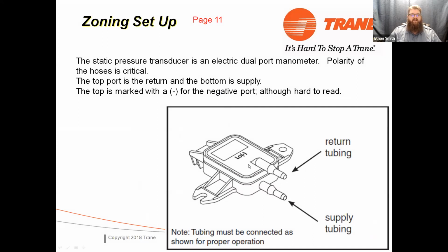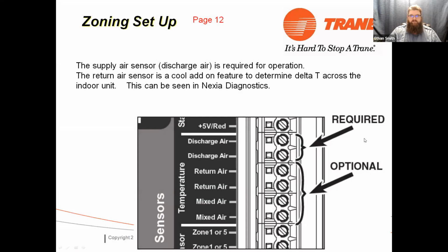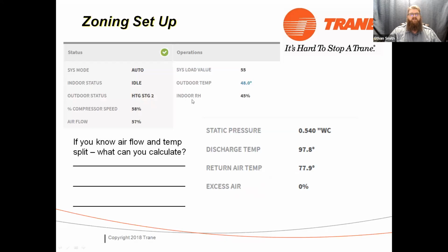It is polarity sensitive. You'll notice on the front of it, it says low or negative. That's going to go to our return pitot tube. Our supply pitot tube is going to go into the back of it. Okay. So our discharge air sensor, like I said, is required. If you don't put that discharge air sensor on, it doesn't work. And we can actually see that discharge air temperature sensor in the Nexia diagnostic screens.